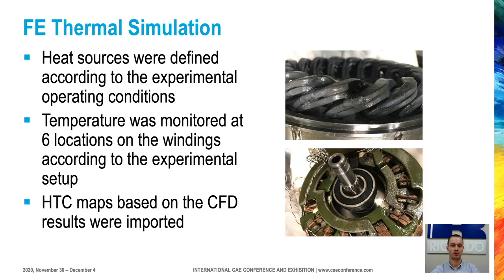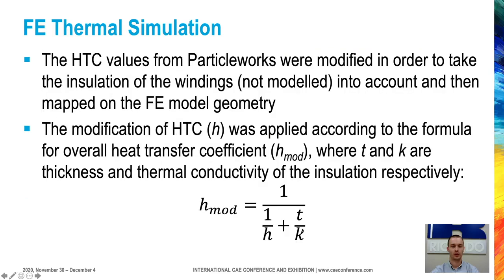The last important input was obviously the HTC map from the CFD simulation, mapped onto the surfaces. However, we could not use the HTC values directly from CFD because there is some coating on the windings that we did not model explicitly in the FE model. So we used the well-known formula for overall heat transfer coefficient and introduced an additional thermal resistance from the coatings — using the known coating thickness and thermal conductivity to reduce the HTC values accordingly.